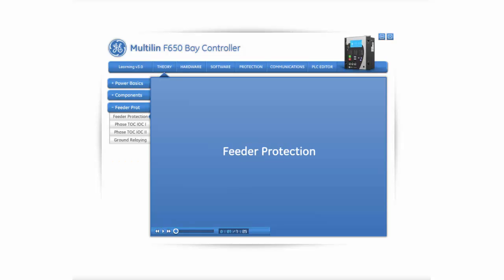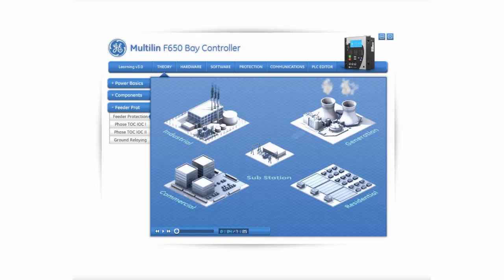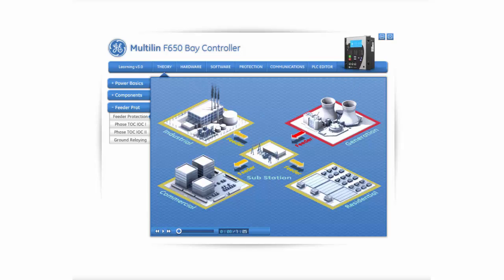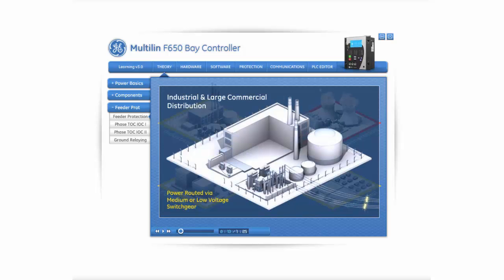Feeder protection is a broad term that refers to sub-transmission lines and distribution circuit protection. Sub-transmission lines refers to lower voltage transmission lines that connect the transmission system to the distribution system. Distribution circuits connect the sub-transmission system to the utilization apparatus. The issues surrounding sub-transmission and distribution system protection are very similar. In most cases, instantaneous and time-over-current protective elements, in addition to directional elements, are the most economical approach for both phase and ground fault protection.